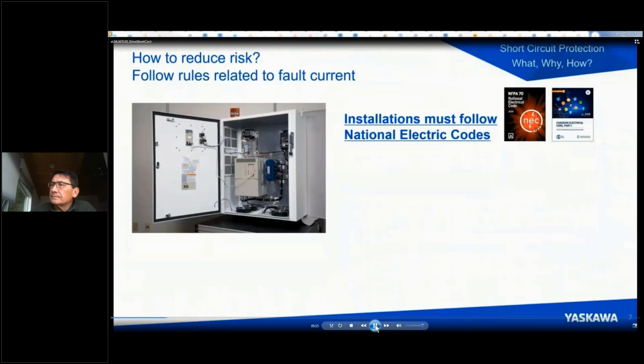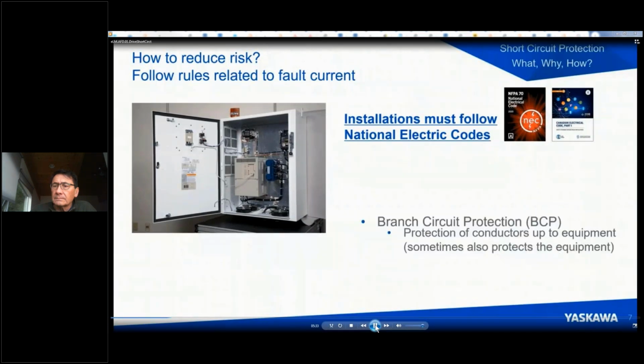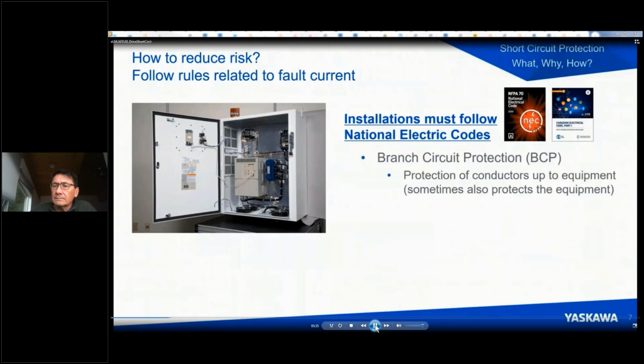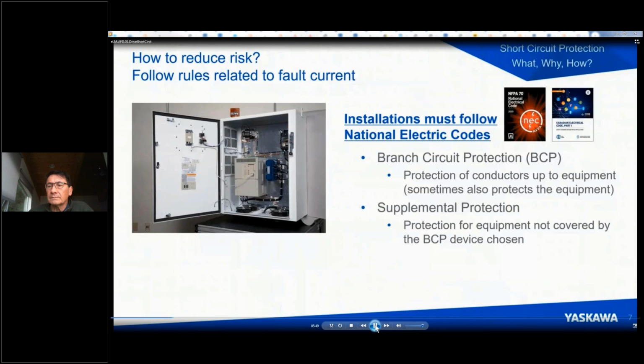So how do you reduce the risk? By following the rules related to fault current. And the rules for fault current are established by the National Electric Codes, that being the NEC for the United States or the Canadian Electric Code for Canada. And it says that you must protect your branch circuit, which is typically the conductors up to the equipment. Now, this same protection, these devices, may often protect the equipment itself, but not always. And in cases where it doesn't actually protect the equipment, supplemental protection beyond what's protecting the wires is required.